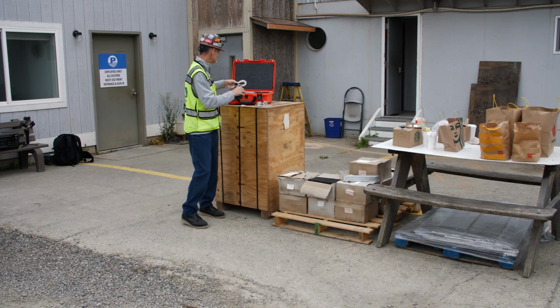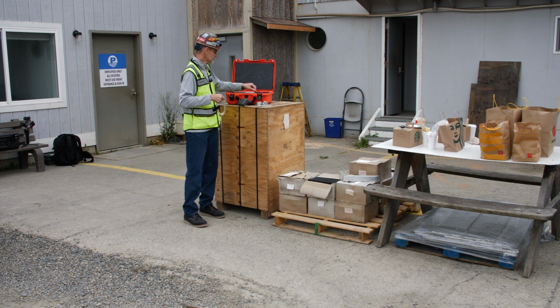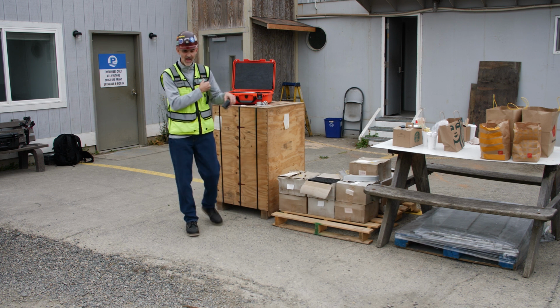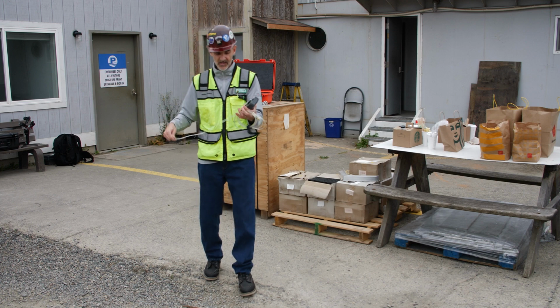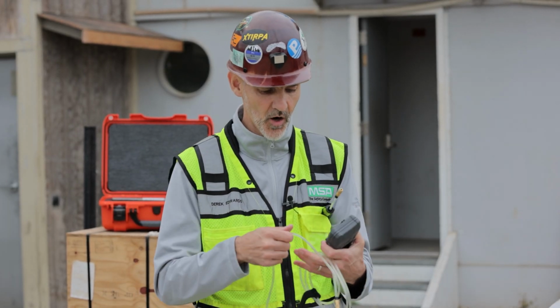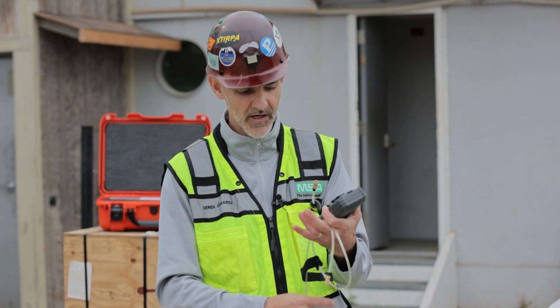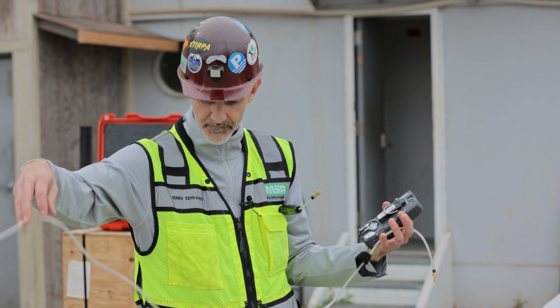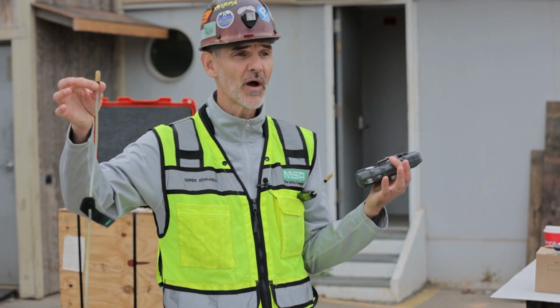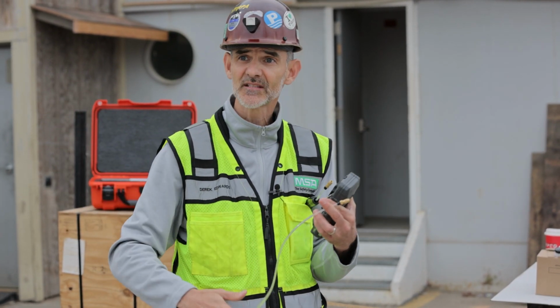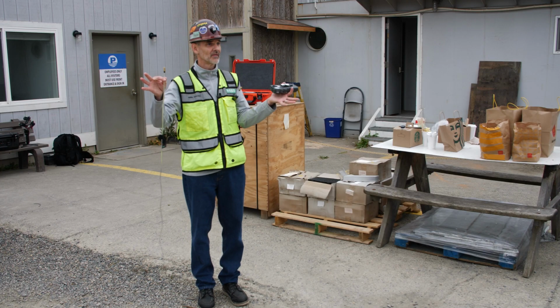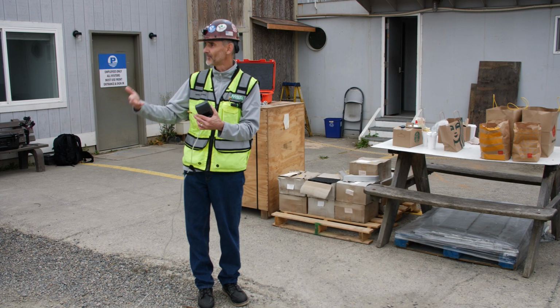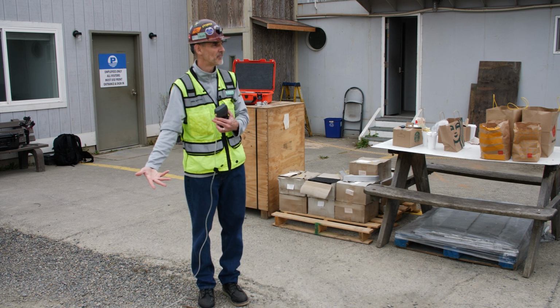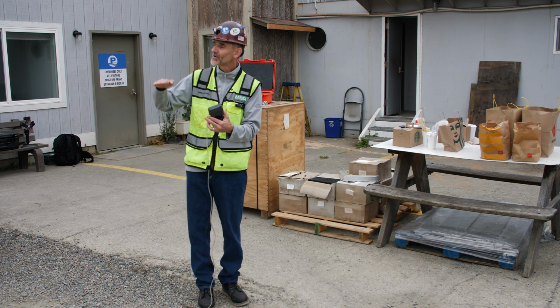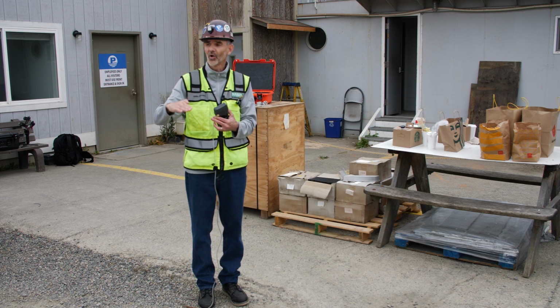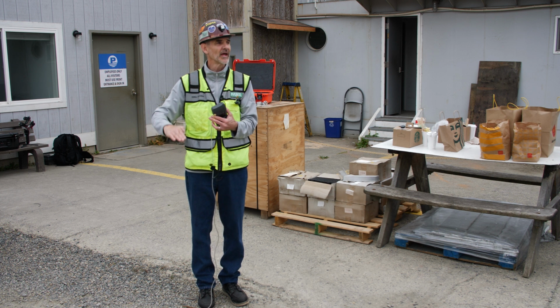So as I mentioned, we have a sample line and probe here because we need to test. We always test the space before we go into the space. So this is a 10-foot line. We do have 20-foot lines, and you can also connect two 10s. If your space is 15, 20 feet deep, this line is not going to be sufficient to test the bottom. So we always start our test at the bottom, and we test about every 3 feet in a confined space, to pull a sample all the way down and all the way up.